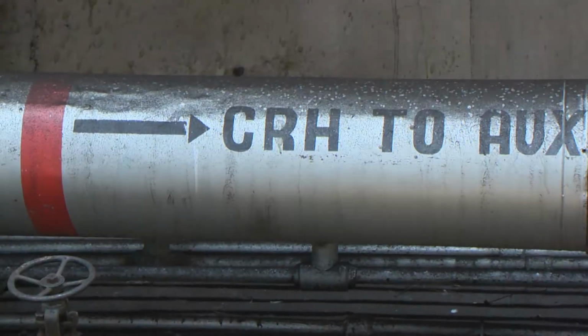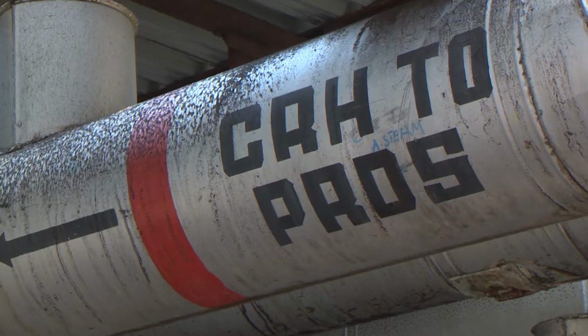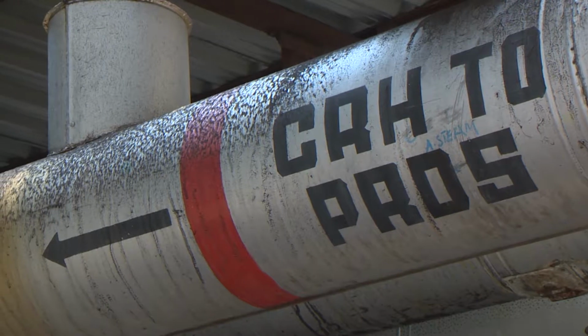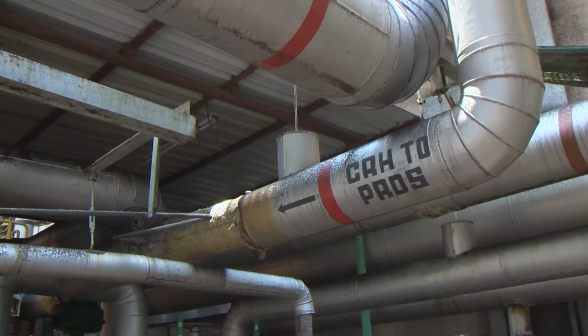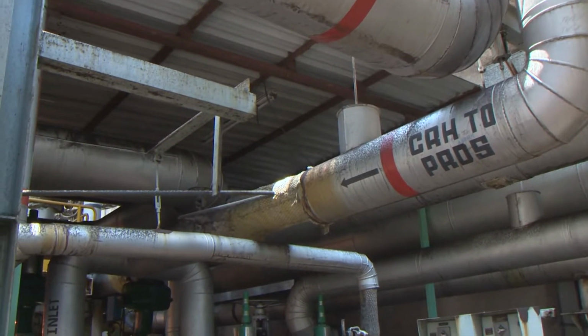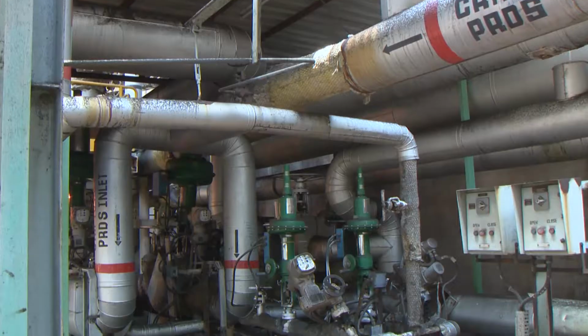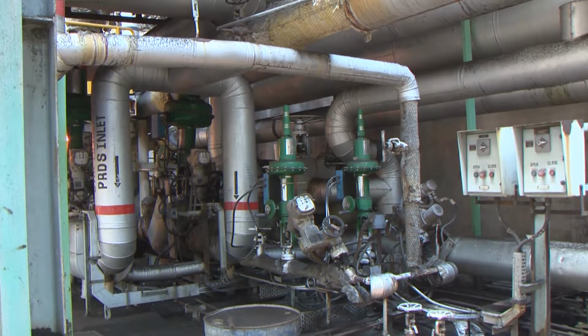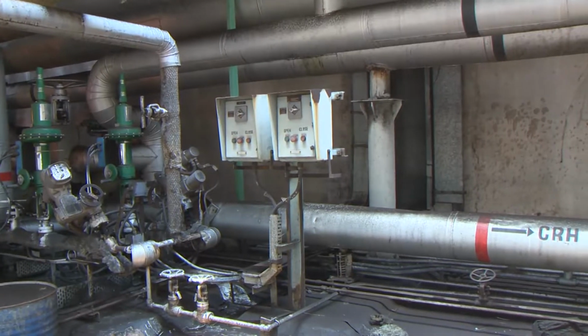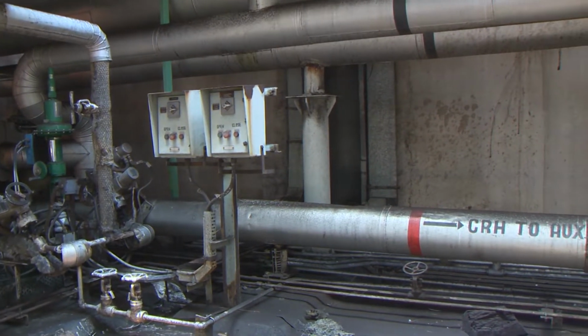Auxiliary steam system. The auxiliary steam system has been provided for meeting the steam requirement of various auxiliaries of the power plant. The steam is tapped from the main steam line or cold reheat line. Then the temperature and pressure are reduced and the steam is supplied to the various auxiliaries.